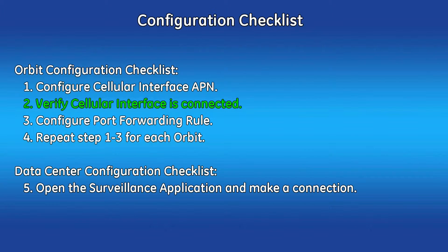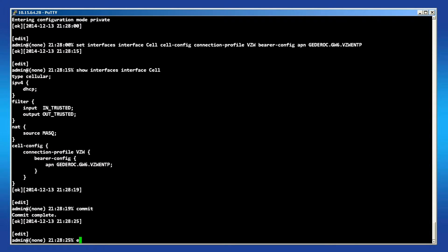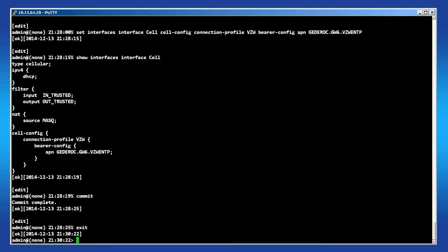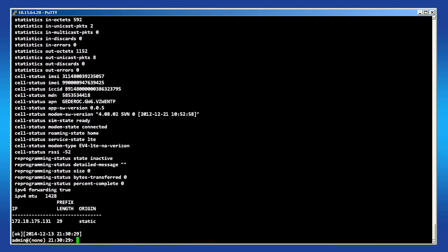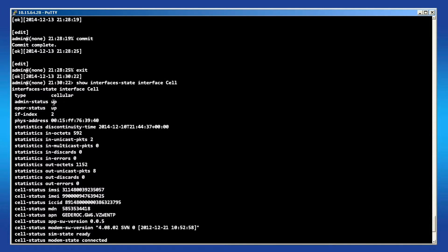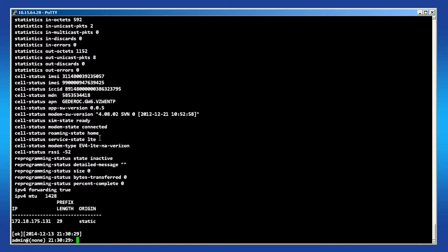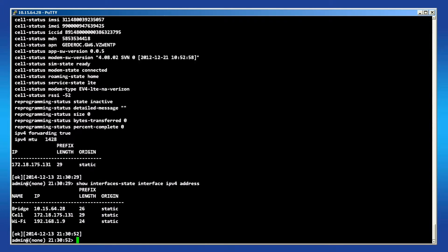The next step is to verify that the cellular interface is connected to your service provider's network. Now that your APN is configured, the interface will begin making a connection with the cellular network. To verify the connection, issue the following command in operational mode. You can view the administrative status, service status, packet statistics, and many other parameters with this command. Then issue the IPv4 command to view the IP address of your cell interface. In my case, it is 172.18.175.131, which will be used to connect to your monitoring equipment.